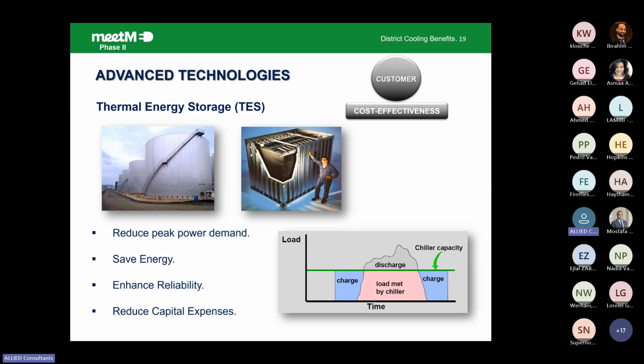If you are planning building by building, then you have the entire power of the building as a chiller in each building. But with a district cooling plant, you can merge and diversify the load between the offices, the malls, and the apartments, sometimes reaching 60% of the peak load of each building. So in conclusion, you can reach less than 50% of the total power demand that you are asking for.